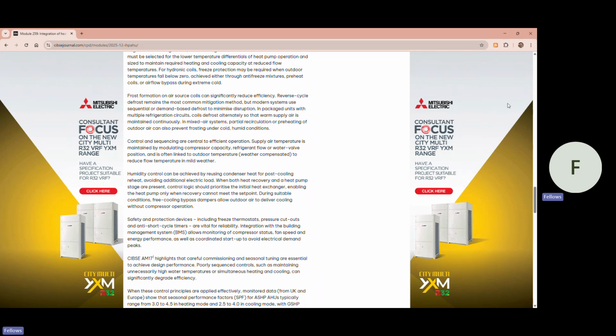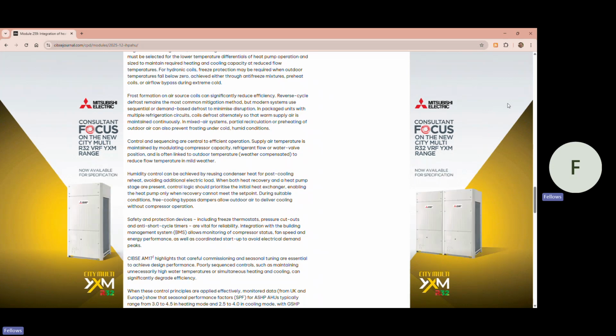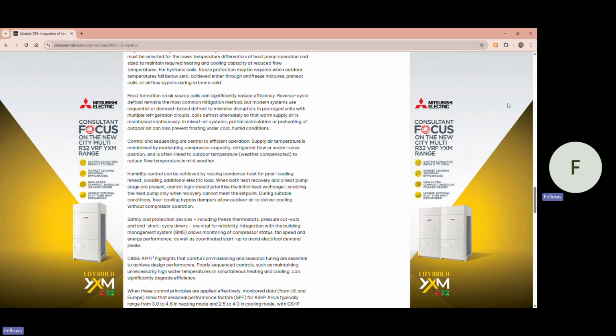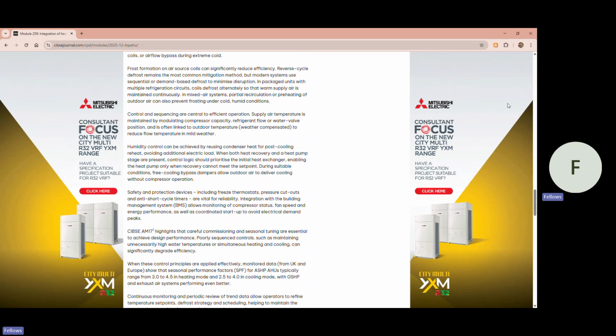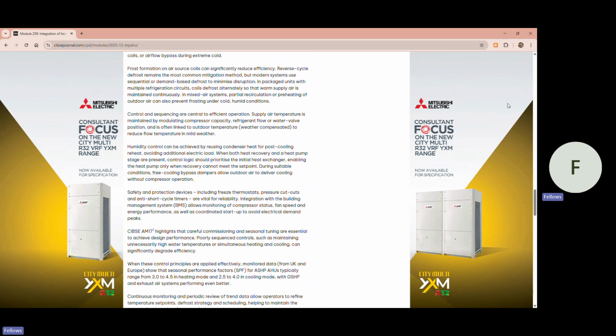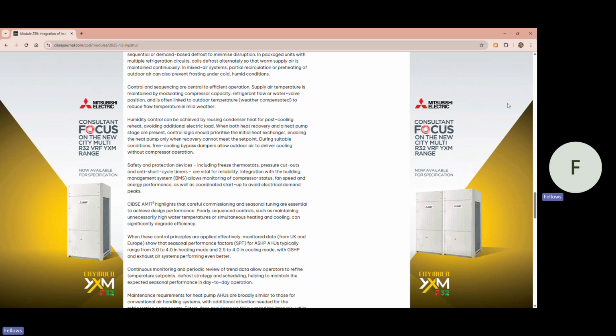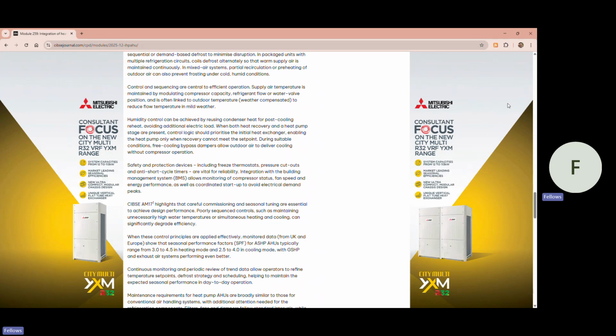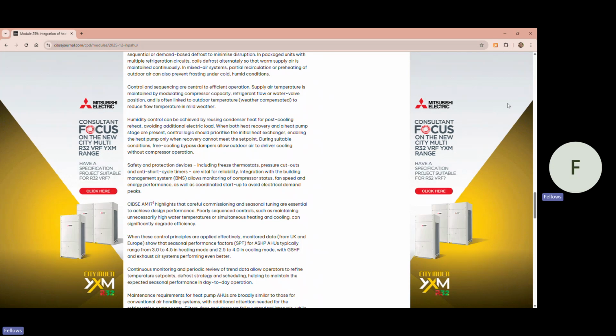When both heat recovery and heat pump stage are present, control logic should prioritize the initial heat exchanger, enabling the heat pump only when recovery cannot meet the set point. During suitable conditions, free cooling bypass dampers allow outdoor air to deliver cooling without compressor operation. Safety and protection devices, including freeze thermostats, pressure cutouts, and anti-short cycle timers, are vital for reliability.